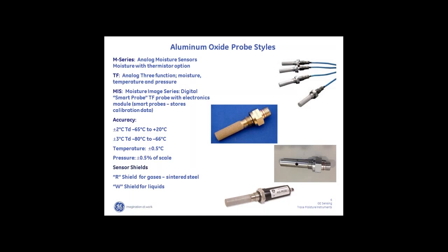With the analog sensors, you have to enter the data into the analyzer. When you purchase one of these sensors, you're given a table of dew point versus impedance data that is entered into the analyzer. These sensors have very good accuracy: plus or minus two degrees dew point above negative 65°C, and below negative 65°C the accuracy opens up to three degrees C. We also equip them with various shields — the R shield is a sintered metal protection, and the W shield has a hole in it, stainless steel, enabling organic liquids to have intimate contact with the sensor.